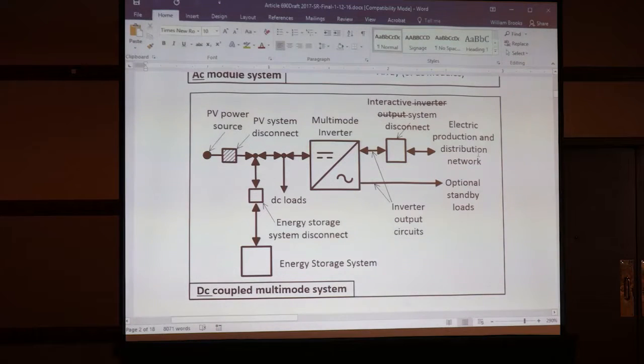And then on the AC output of this, there's two AC outputs of a multimodal inverter typically, correct? The reason we call it a multimodal inverter is one mode is connected in a grid-connected mode, and the other mode is a standalone mode, right? And so what we have is the interactive system disconnect, which goes to the utility system, or it could go to other electrical distribution networks, because it might not be the utility. It could be a microgrid. It could be all kinds of different things. That's why we use this more generic term. And then we have the optional standby loads, or the standalone loads that this thing is serving. And that's covered by the load section of the code. Does that make sense?